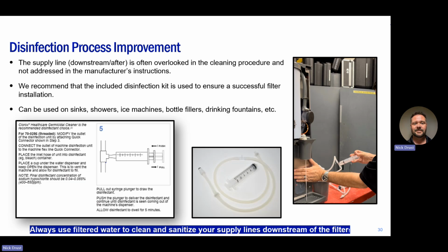Think about what happens during a filter replacement. We remove the old filter. We install the new filter. What about the tubings, fittings, dispensers, and components that were connected to an old filter? You want to make sure that you have eyes on this and that those are being changed as well. That's really the theme here with 514. We're going to look beyond the obvious fixtures and identify hidden risks throughout that entire water pathway.